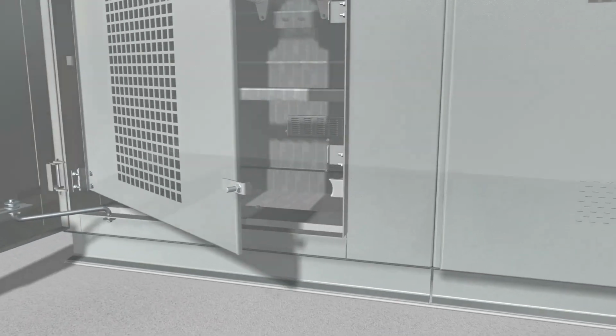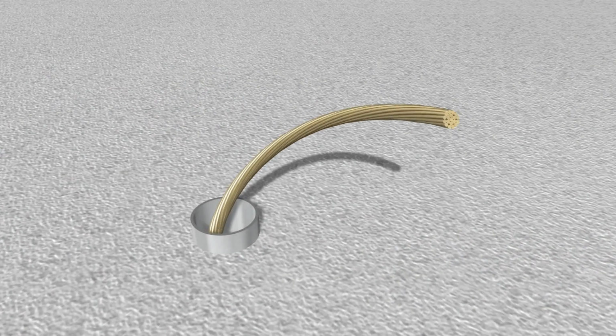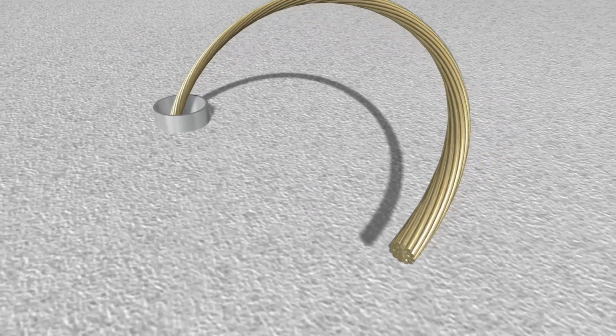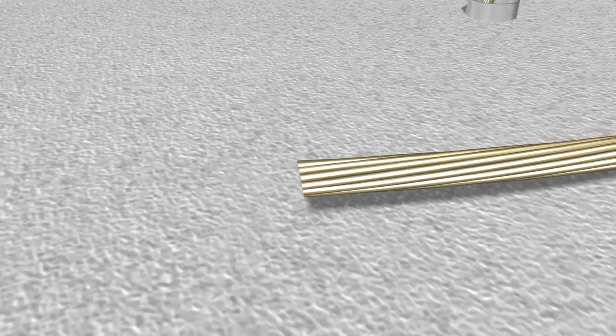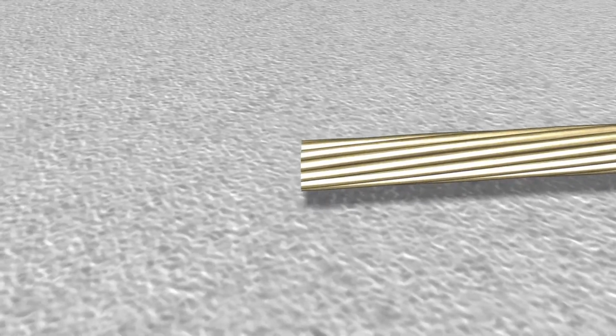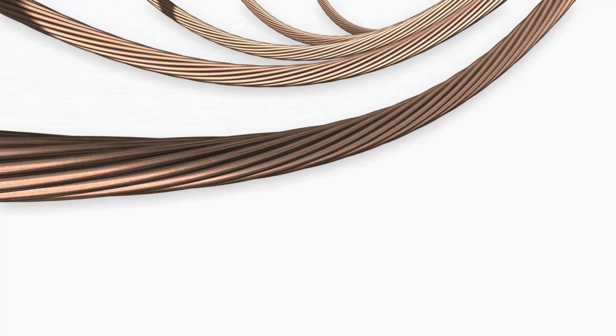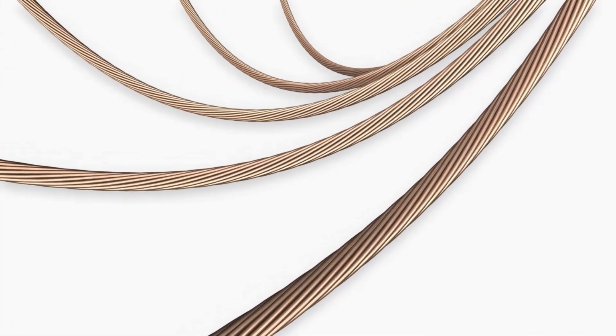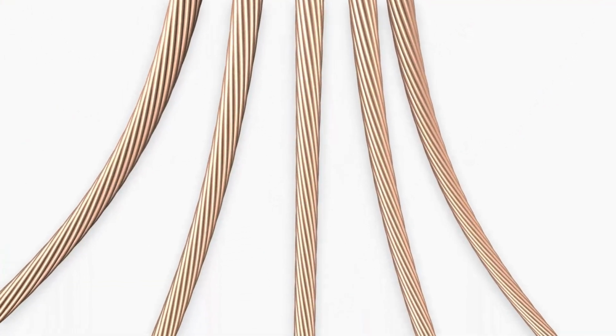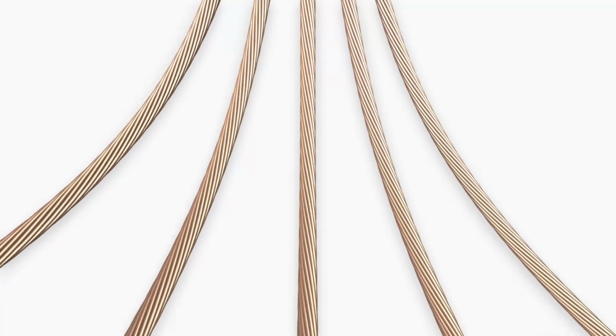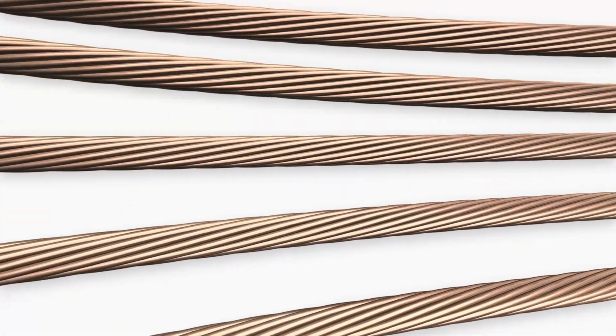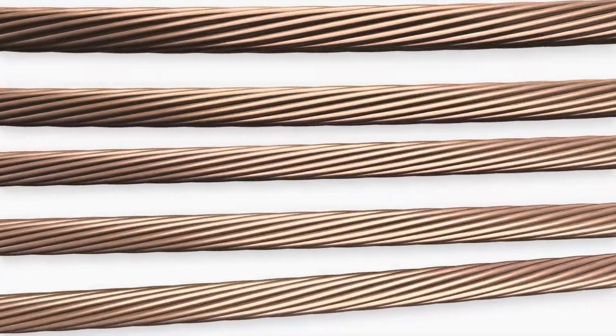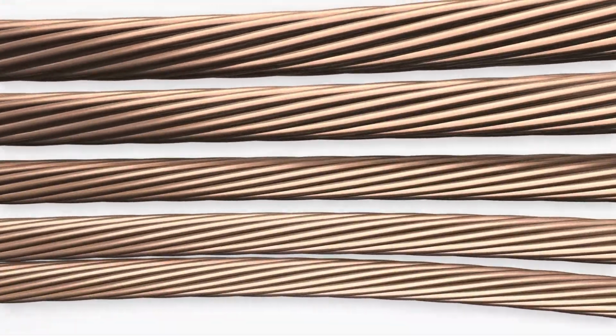Step 10. Make ground connections from the ground bus, or ground pad on a single bay assembly, to the permanent station of the system ground facility. S&C recommends cable not smaller than 1/0 copper or equivalent be used. And if the maximum momentary rating of the switchgear is to be realized, the equivalent of 500 kcmil of copper cable is required in either a single or multiple connection.